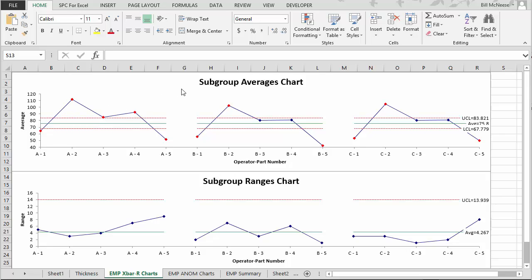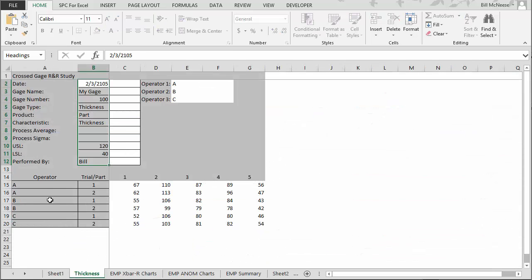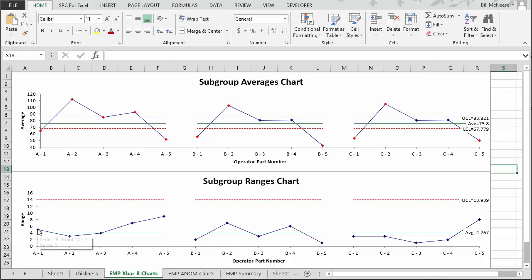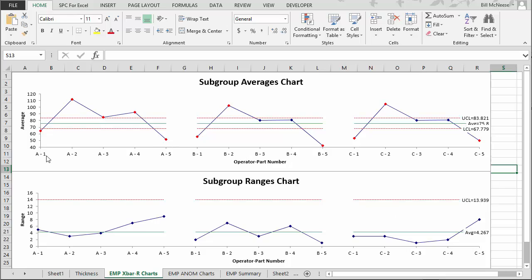Remember what we said about the X-bar and R charts: we take a subgroup formed of each combination of operator and part number, plot the average of that subgroup on the X-bar chart, and the range on the R chart. For Operator A's first result, he had 67 for trial one and 62 for trial two with part one — average is 64.5, plotted on the X-bar chart. The range of 5 is plotted on the range chart. We do that for all combinations from Operator B part one all the way to Operator C part five, calculating averages and control limits using classical X-bar and R chart calculations.